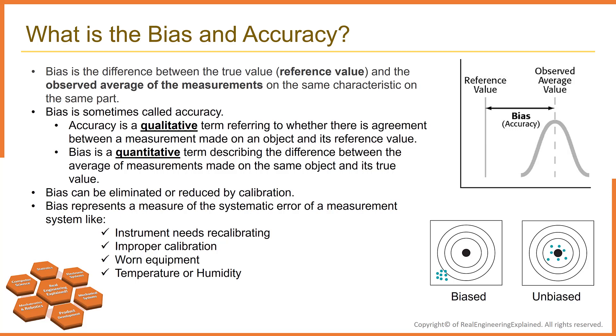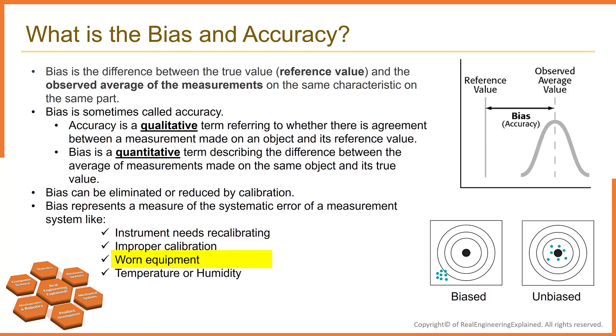Accuracy and bias refer to the absolute correctness of the measurement system relative to a golden sample or gauge block. Bias represents a measure of the systematic error of a measurement system. Sources of bias include: instrument needing recalibration, improper calibration, worn equipment, damaged master or golden sample, and temperature or humidity.